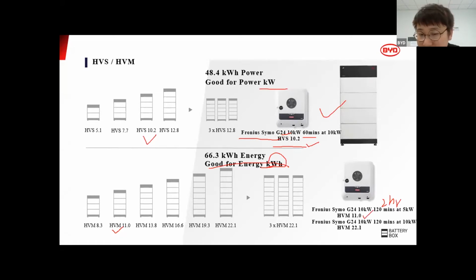And is that possible, I can still use the HVM and discharge at 10 kilowatt with Fronius? Yes, definitely you can, but you just need to oversize your batteries. So with the 22.1, for example, you can also discharge or charge the battery at 10 kilowatt. Is the 10 kilowatt, or the 1C charge or discharge rating of the battery, important for the customer? For most scenarios, it's not really.